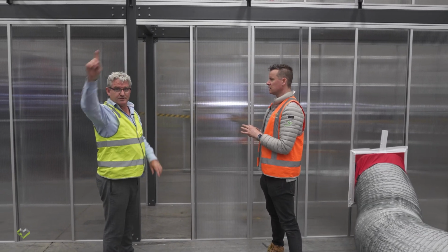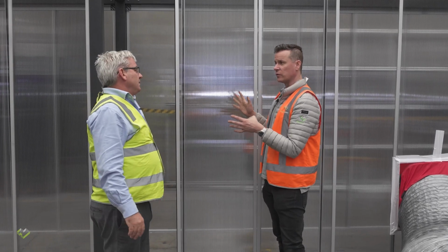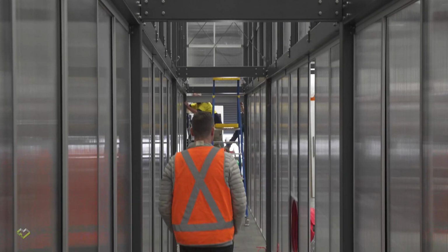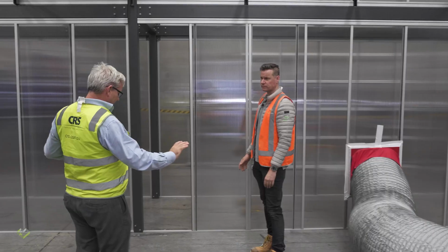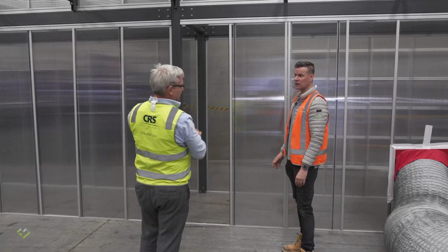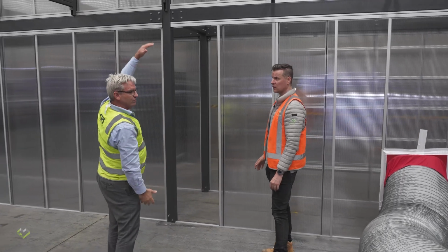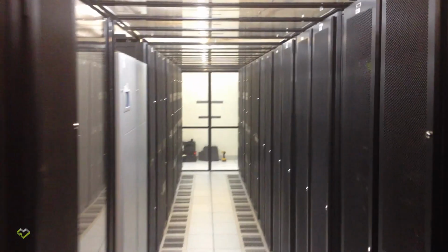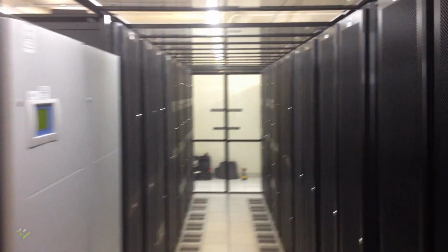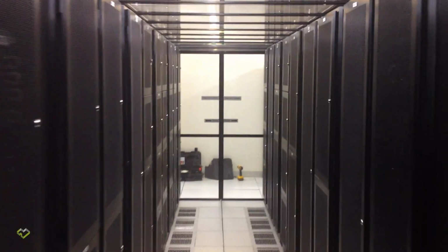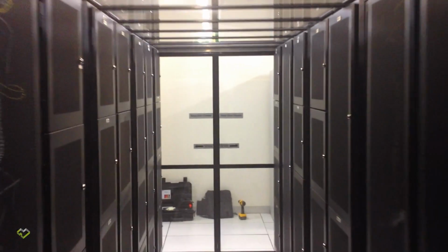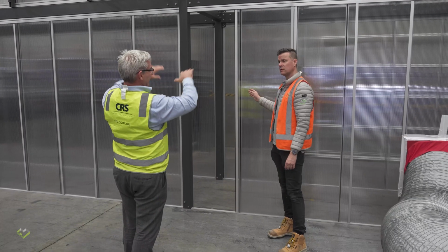Simple reticulation. So it's also extremely critical that the racks that are going in maintain their spaces when there's servers and stuff that are missing. Oh, definitely. When your racks are in there, you need blank panels. If you haven't got a full complement of equipment in the rack, you don't want any return hot air going back through the rack and back through gaps that are in the front of the rack. So it's critical that you blank all that rack off down the sides and in each rack unit.